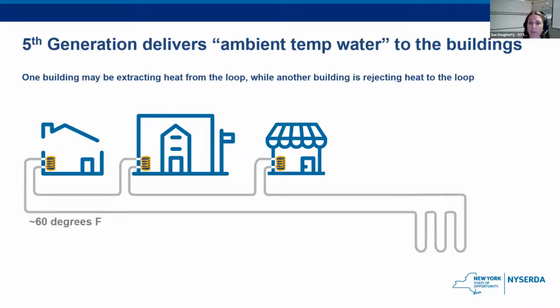One advantage of an ambient style system is that thermal resources can be shared between buildings. One building might have a higher heating demand, while another has a cooling demand, and the building with the cooling demand can send its rejected heat to the building that needs it.